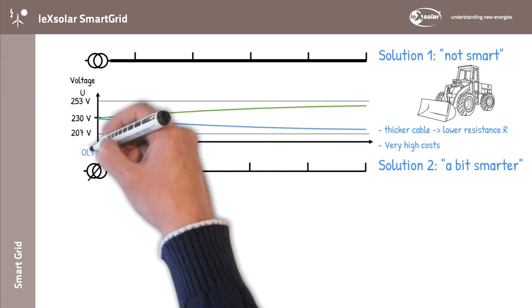A smarter solution would be to replace the transformer with an on-load tap changer, a transformer that can adjust the transmission ratio and thus the output voltage. Based on a measurement of the voltage at the end of the street at house 5 or the power transformer, the output voltage of the transformer could be controlled this way. So in the summer scenario, the voltage at the transformer could be reduced, and in the winter scenario, the voltage could be increased, so that in both scenarios, all voltages are within the voltage band.